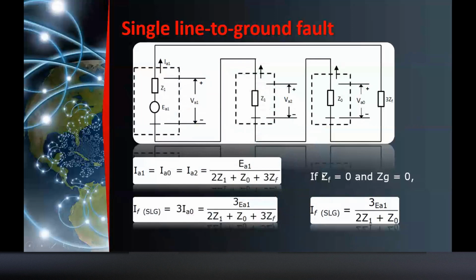Coming to the single line to ground fault, it is this. Your I fault for a single line to ground fault is simply 3 EA1, or sometimes you will see 3 V per unit, divided by 2Z1 plus Z0. Originally it is Z1, the positive sequence impedance, plus Z2 plus Z0. In a power system, Z1 and Z2 are sometimes equal, so it is simply written as 2Z1 plus Z0. So this is what you remember for a single line to ground fault.